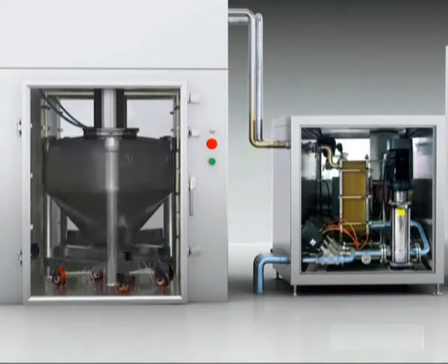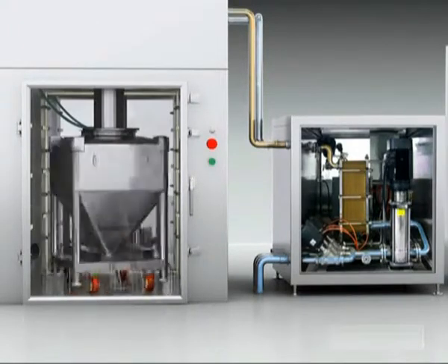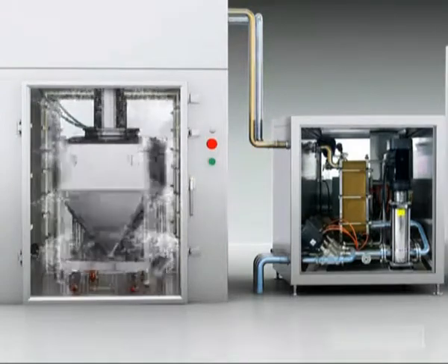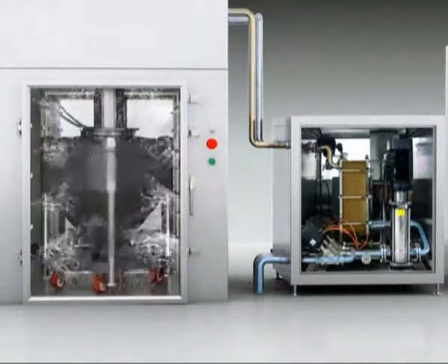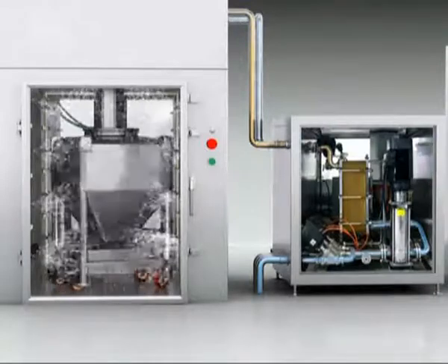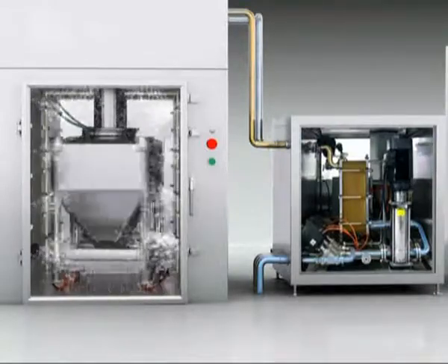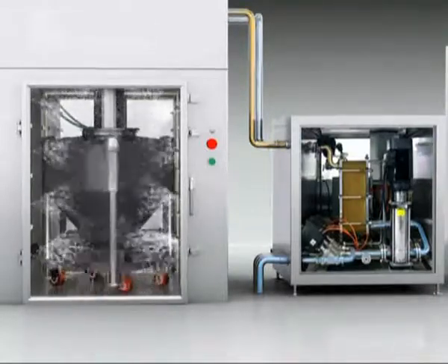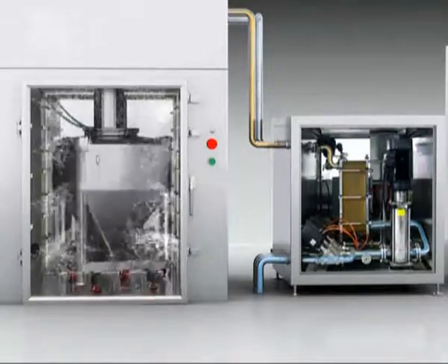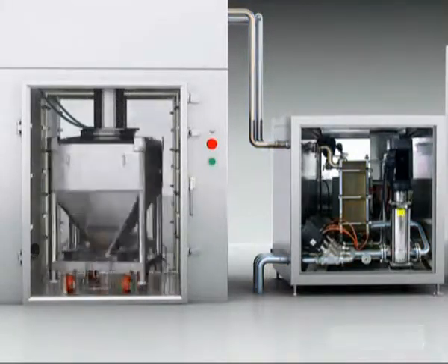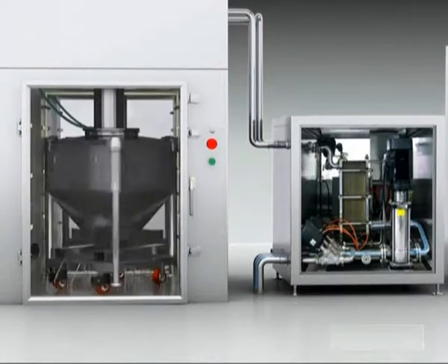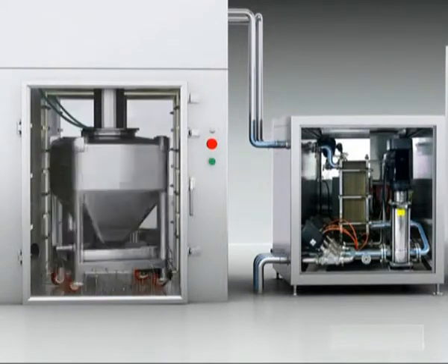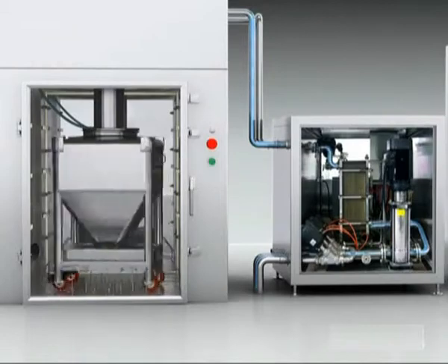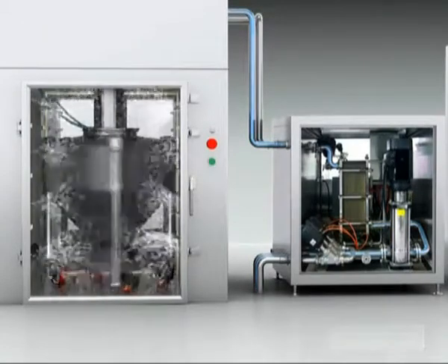After the hot water washing procedure, the system loads automatically the detergent washing procedure. In this stage, the detergent unit in the pump station prepares the detergent solution, and the boost pump increases the pressure of the detergent solution. Then it flows through the piping to the top washing board and the nozzles on the washing chamber walls for bin internal and external surfaces cleaning.